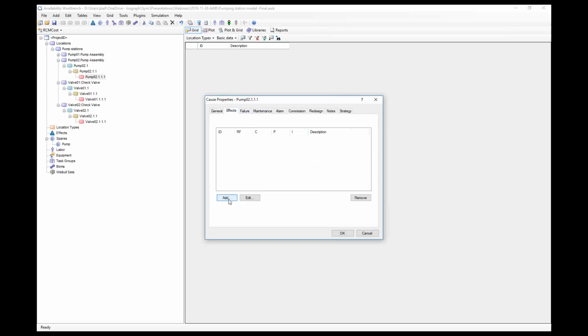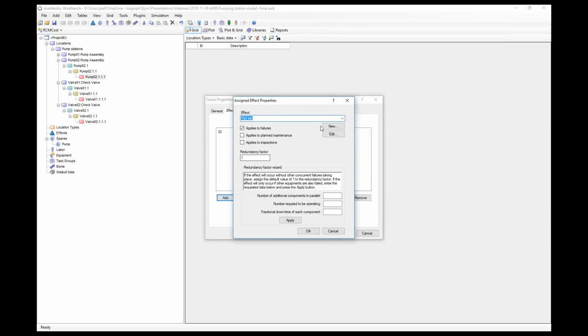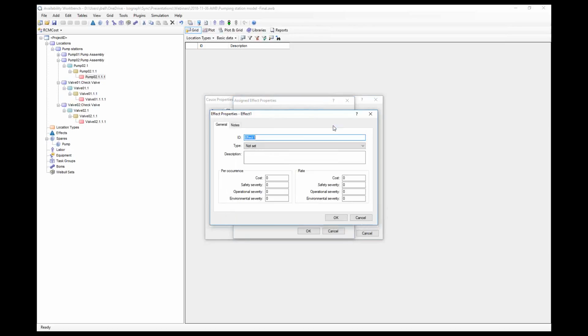So I'm probably going to want to set up an effect in RCM cost. What's the effect of failure? It costs the failure of the pump - we dropped 25% capacity, which I said was going to be about $100 per hour per unit capacity, so multiply that by 25. We'll say it's $2,500 per hour to lose one pump on average.